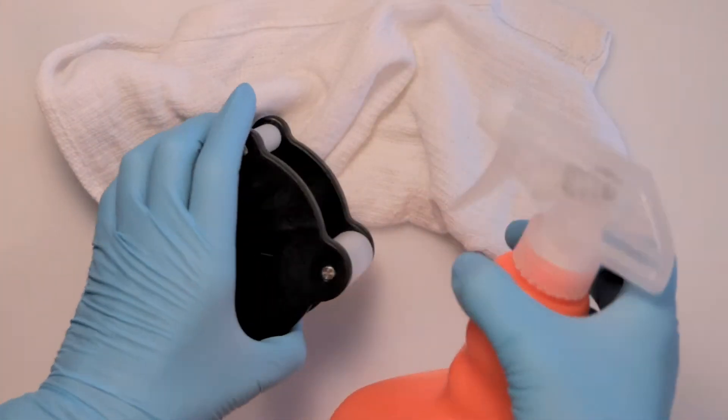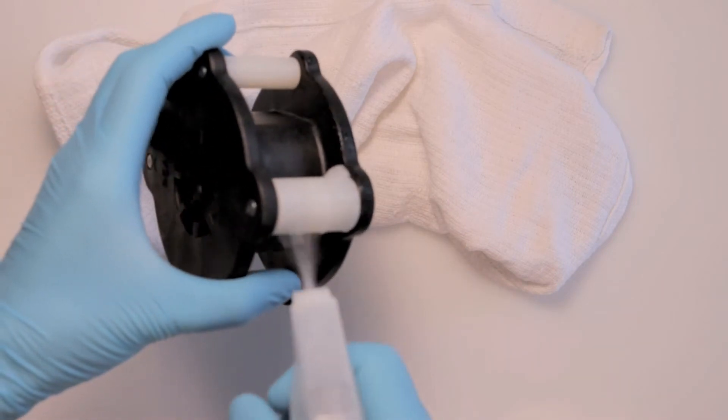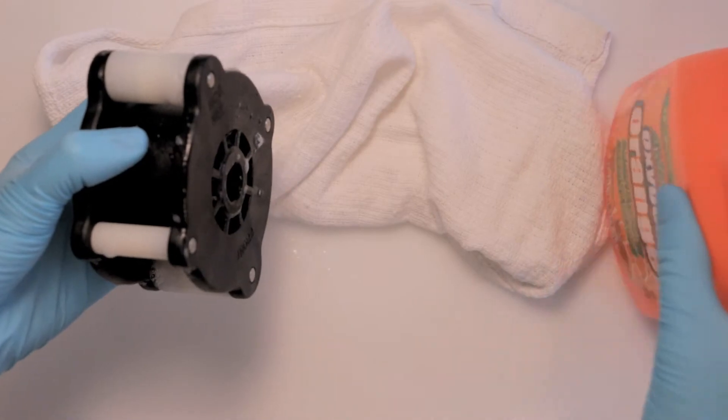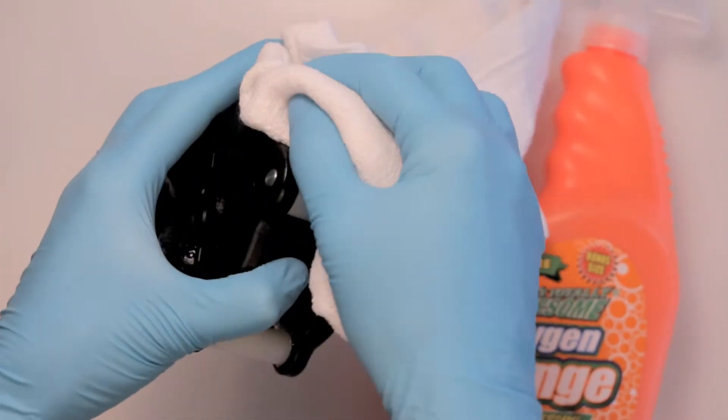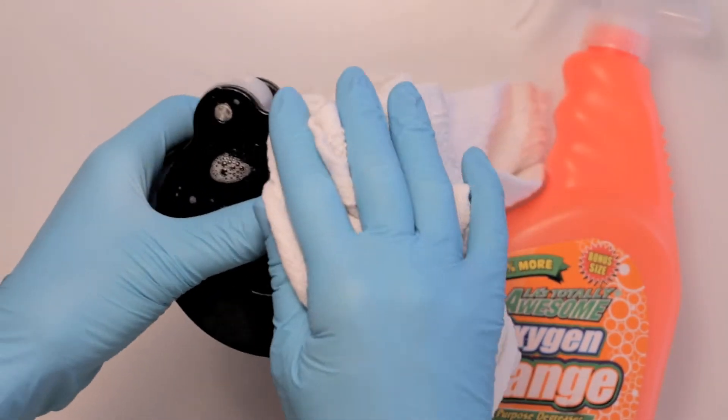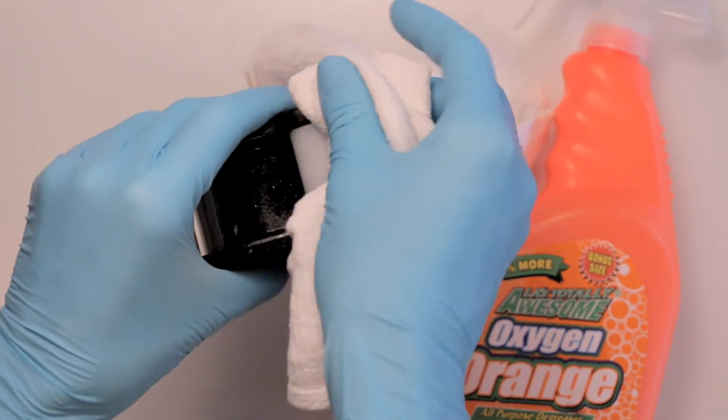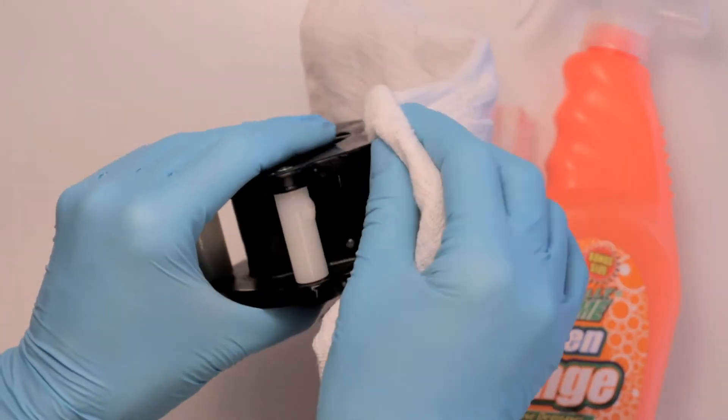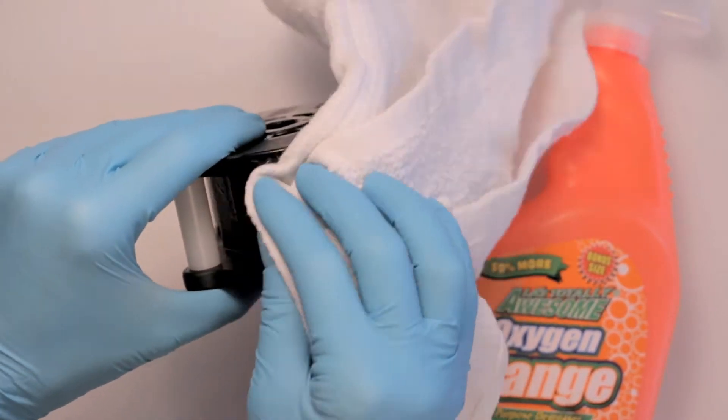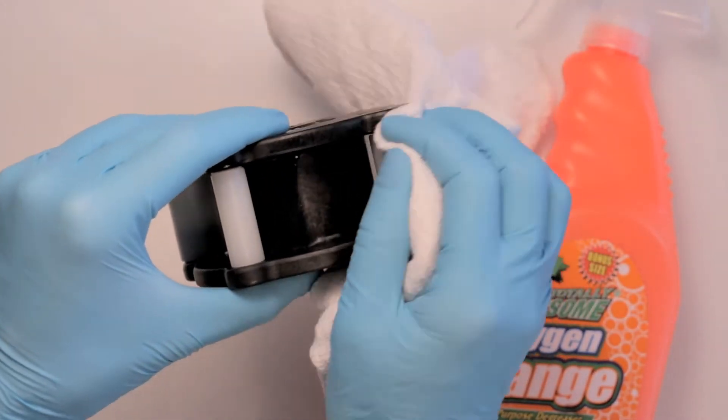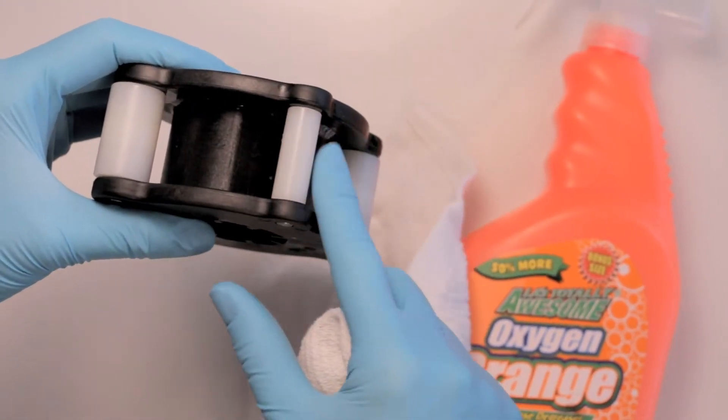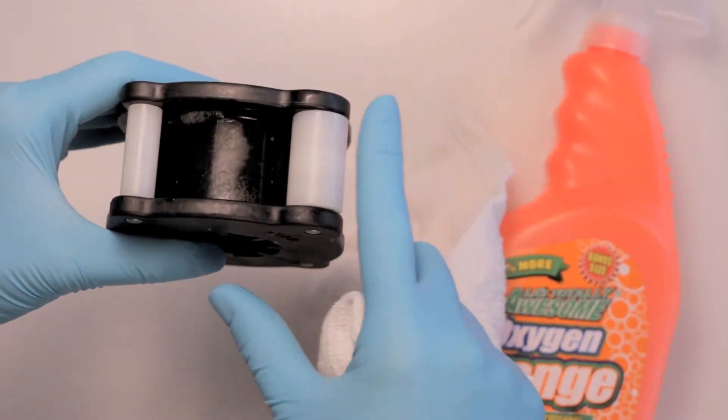Remove any debris, chemical, and grease from the roller assembly with your degreaser and rag. You'll want to verify the rollers are free spinning. Any seizing of these parts will cause extra friction and wear on the tubes.